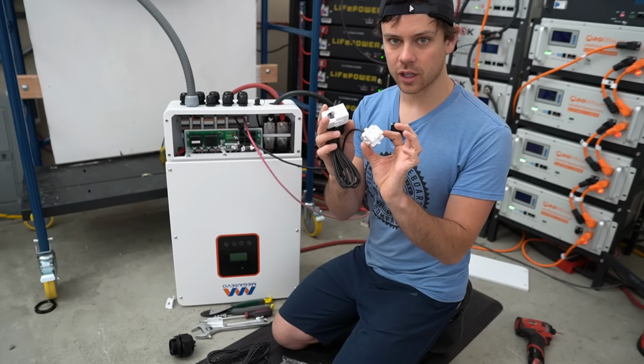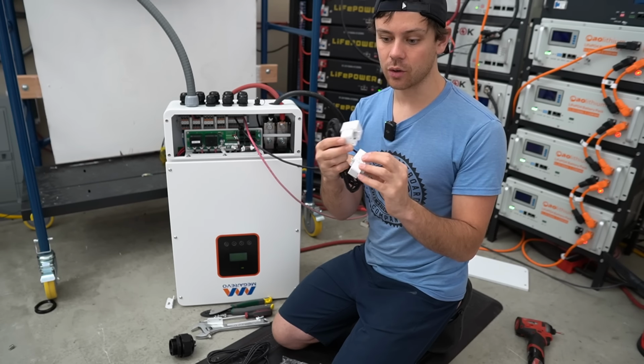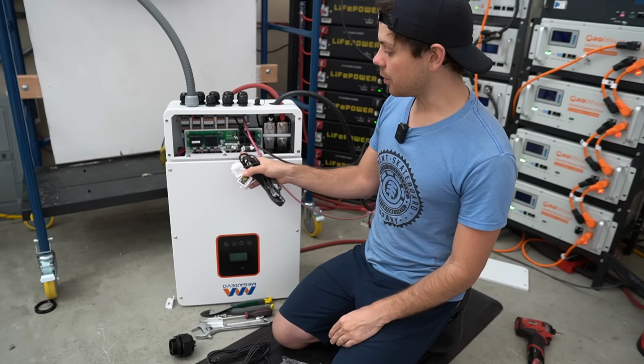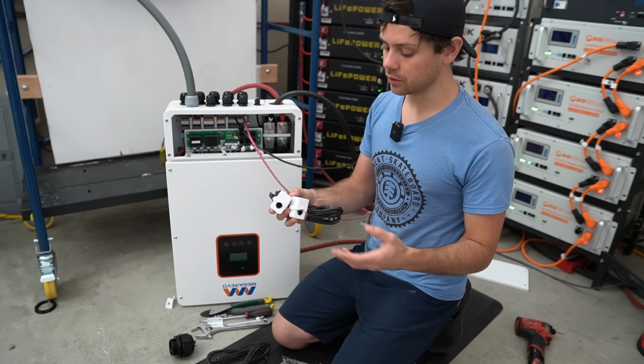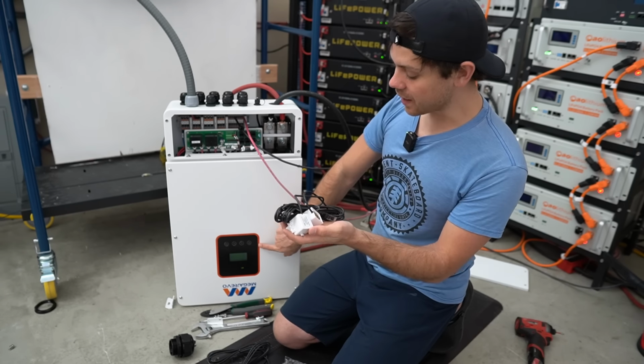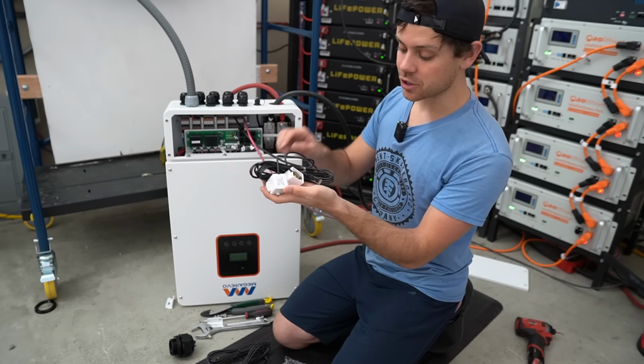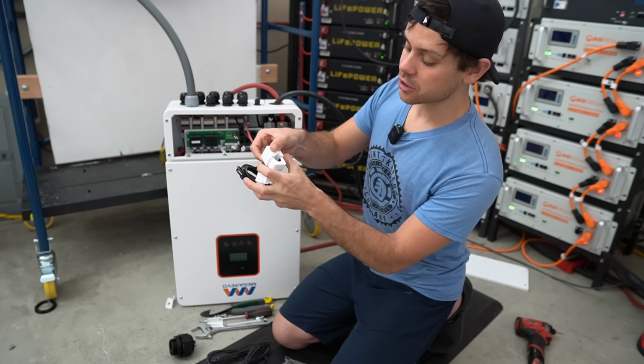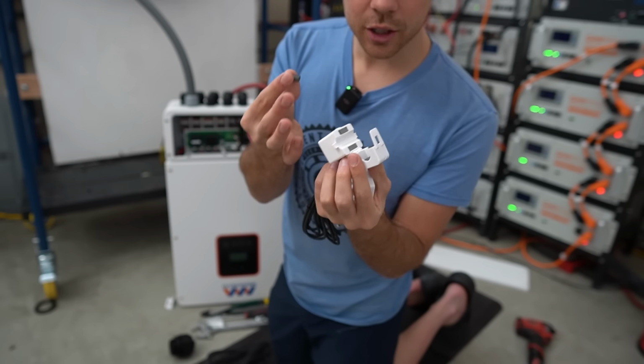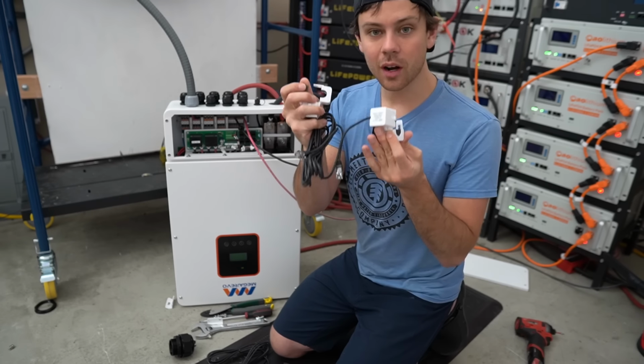And these are current transformers. These sense how much current is going in and out, and it will compensate how much this will feed to offset the loads. The CTs that arrive with the Megarevo actually arrive damaged. The cover is missing, and there's actually quite a few parts that are broken. These pieces actually broke off, so this is unusable. Oh wow, they broke off on both of them.